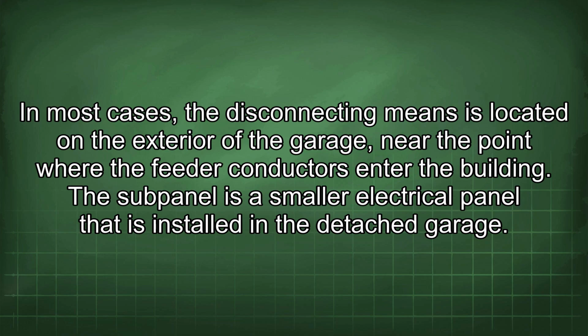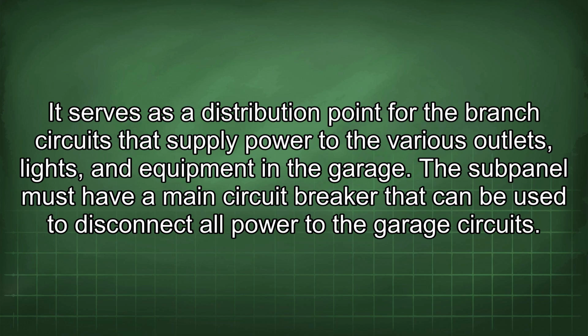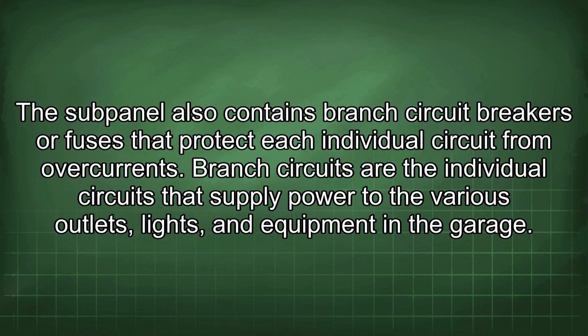The subpanel is a smaller electrical panel that is installed in a detached garage. It serves as a distribution point for the branch circuits that supply power to the various outlets, lights, and equipment in the garage. The subpanel must have a main circuit breaker that can be used to disconnect all power to the garage circuit. The subpanel also contains branch circuit breakers or fuses that protect each individual circuit from overcurrents.